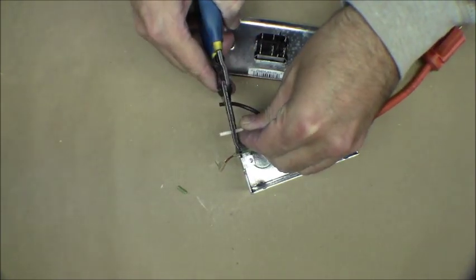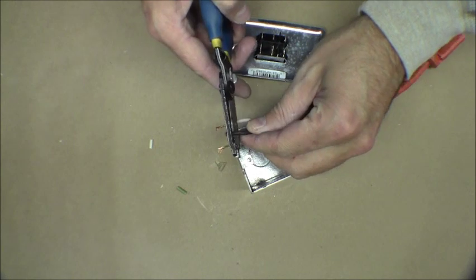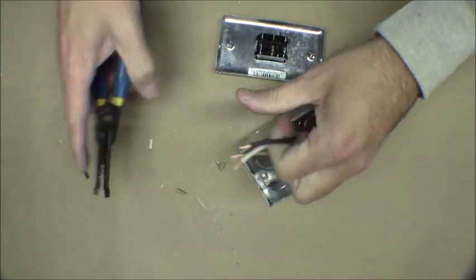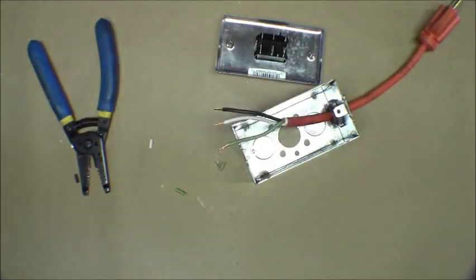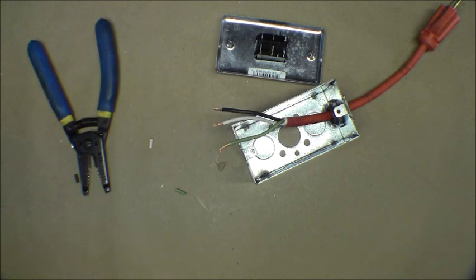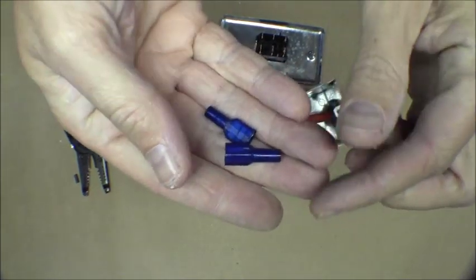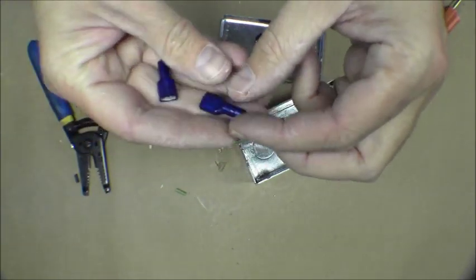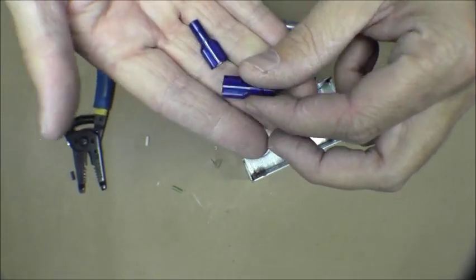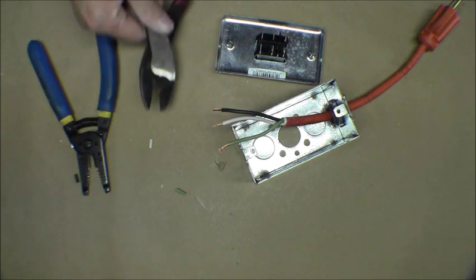I'm going to use fully insulated female connectors. Generally the bluish ones are rated for the 14 gauge, which is what this wire is. And the 14 gauge is good for 15 amps.